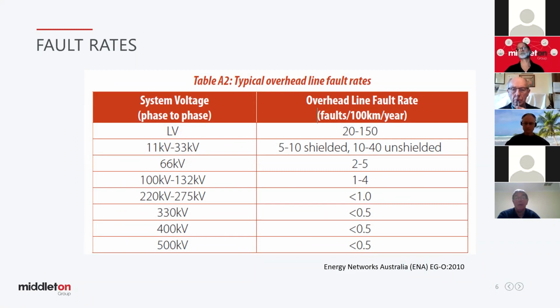Interesting to have a look at fault rates. We mentioned fault rates as one of the probabilistic inputs on the last page. We mightn't think there's too many faults around our suburb. However, when you stop to think about it, there's a zone substation supplying the power in your area. If you've got copper water pipes in your house, they'll be bonded to the neutral that goes out on the street, which, depending on the state and the area, could well be common bonded, or CMEN as we call it, and in those terms it's likely that your taps in your house can be bonded all the way back to the zone substation.